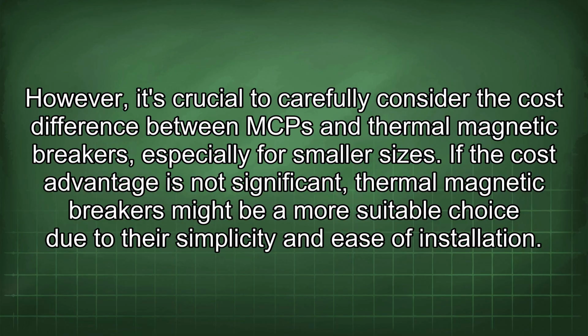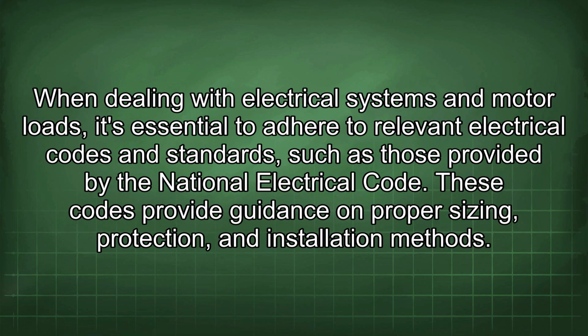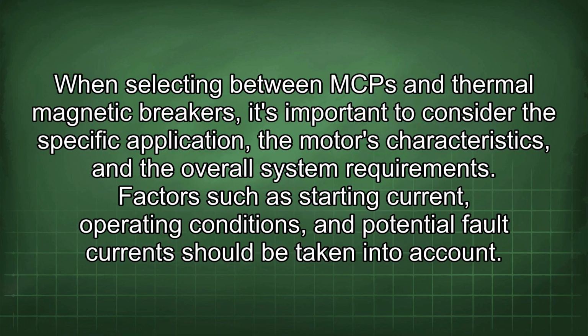When dealing with electrical systems and motor loads, it's essential to adhere to relevant electrical codes and standards, such as those provided by the National Electrical Code. These codes provide guidance on proper sizing, protection, and installation methods. When selecting between MCP and thermomagnetic breakers, it's important to consider the specific application, the motor's characteristics, and the overall system requirements. Factors such as starting current, operating conditions, and potential fault current should be taken into account.